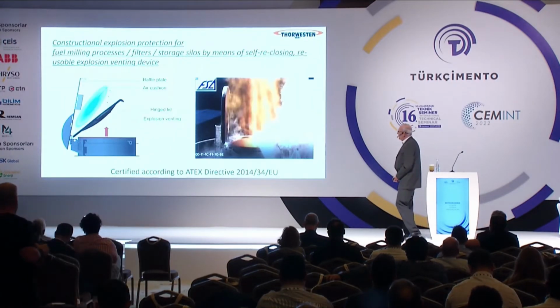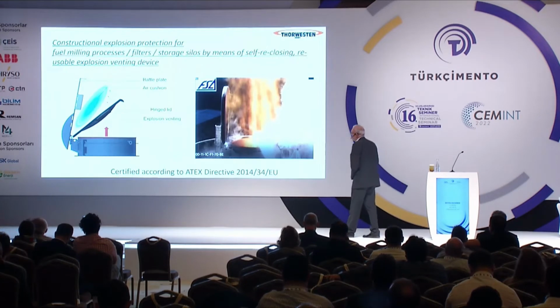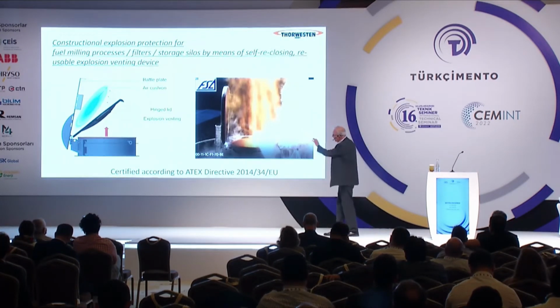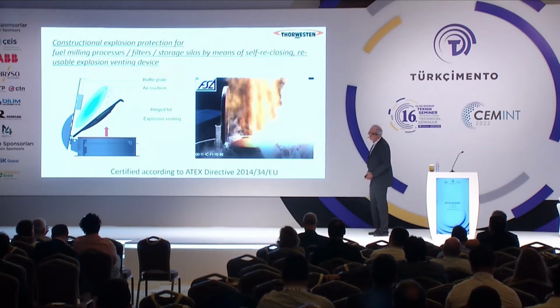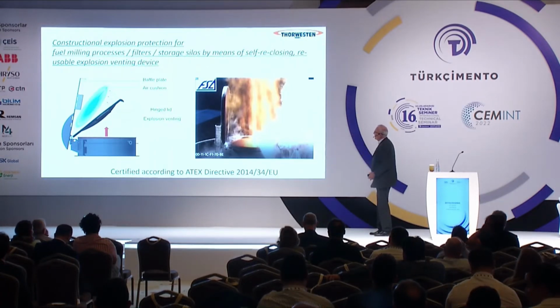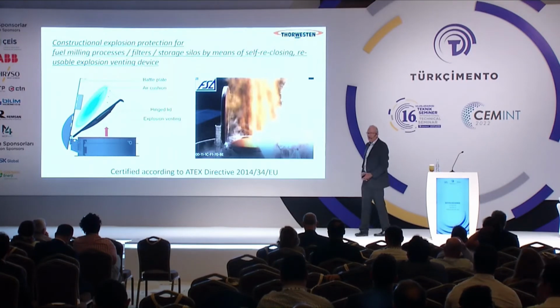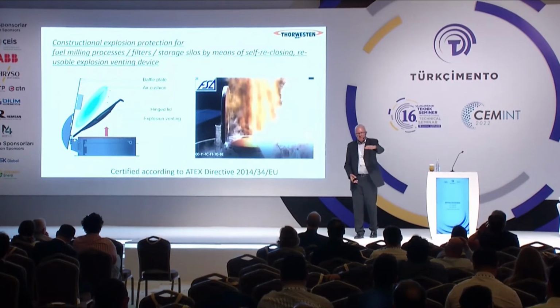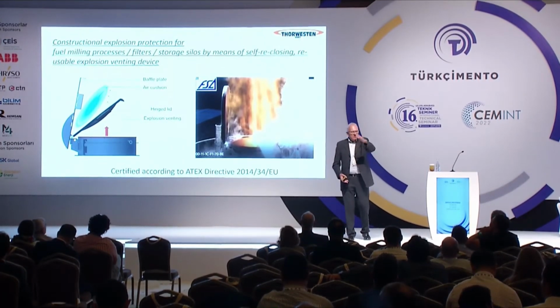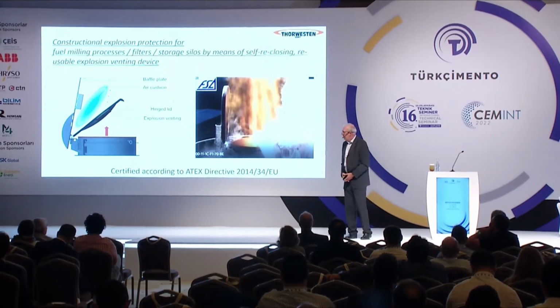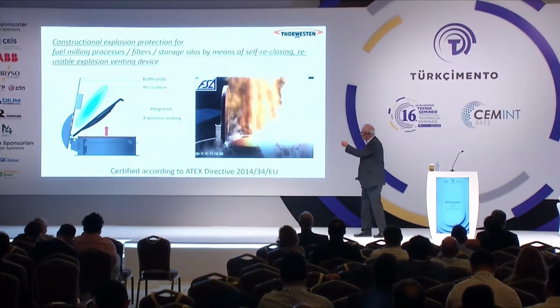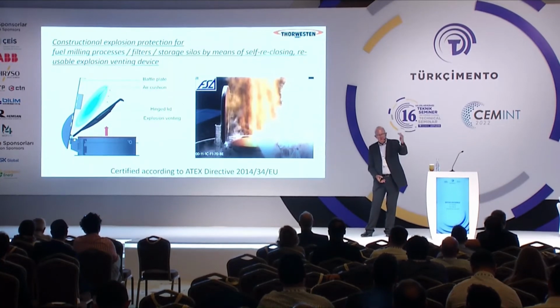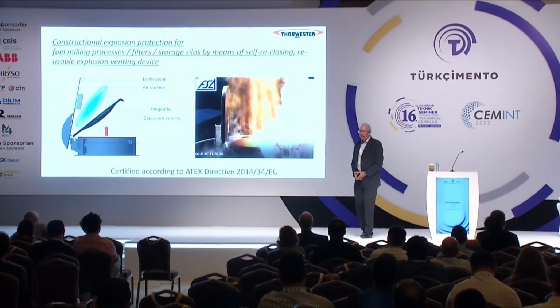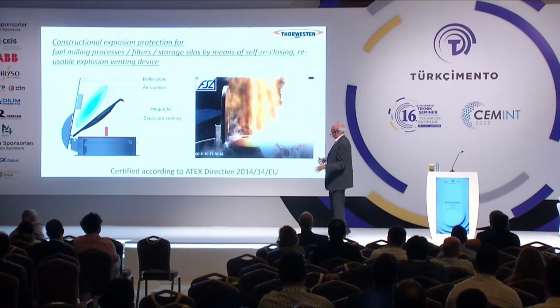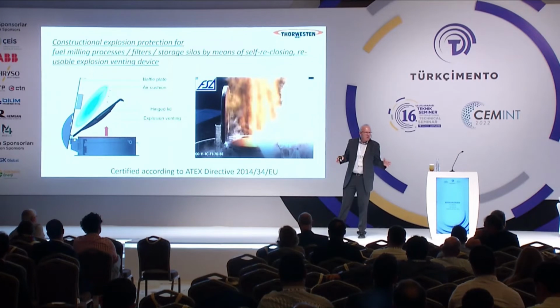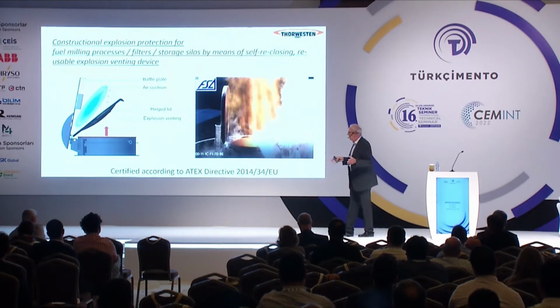Constructive explosion protection, just a brief introduction. What does self-reclosing mean? Here the gray cover is the frame of our explosion door. The black one is the hinged lid, and the gray one is the baffle plate. Usually it's closed. If a certain activation pressure is exceeded, the hinged lid opens. Kinetic energy is absorbed by the air cushion principle and the baffle plate, and finally the lid is pushed back into the closed position and kept closed by retaining devices. This is the basic principle of our self-reclosing explosion venting devices, to keep the system closed.